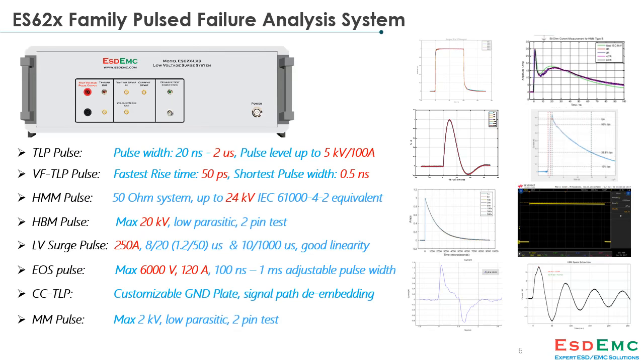One of our more popular product lines is our ES62X family. This allows for the automated ESD and EOS testing of devices and will allow for automatic failure analysis as well, typically using an SMU for leakage measurement. Our more popular products in this line are TLP and VFTLP. Our TLP goes from 20 nanoseconds to 2 microseconds pulse width and can pulse up to 100 amps across a short, 5 kilovolts across an open. Our VFTLP has rise times down to 50 picoseconds and half nanosecond pulse widths.